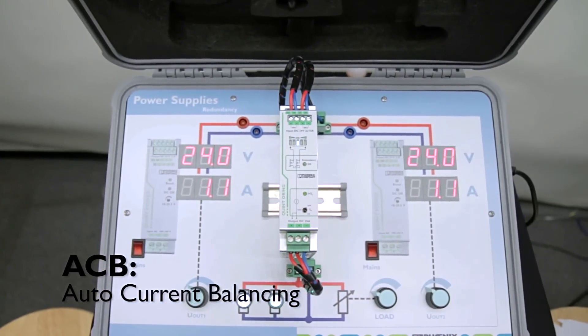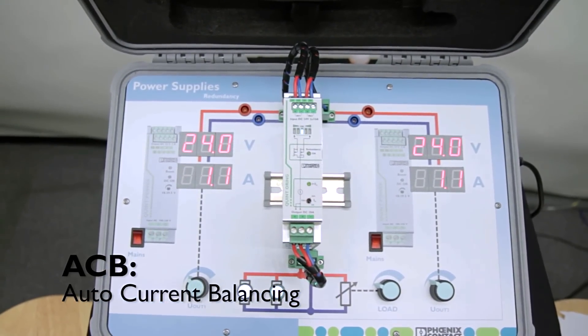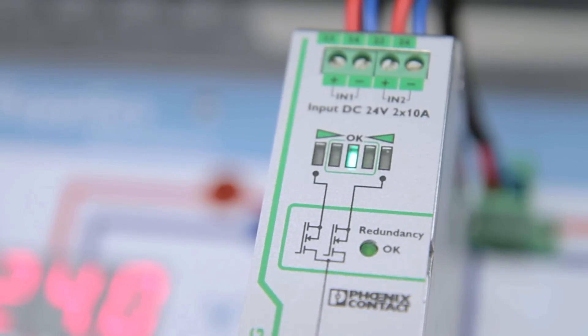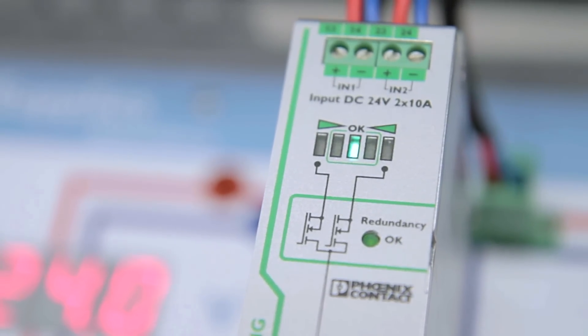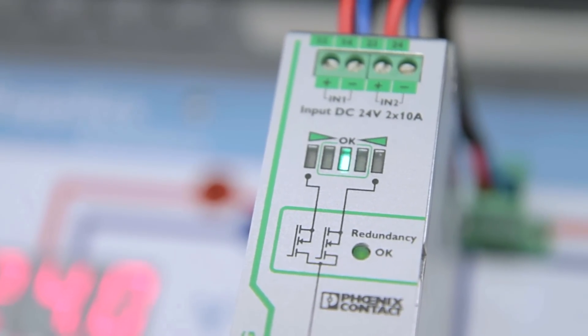The QUINT ORING modules use Auto Current Balancing, or ACB, technology to ensure the power supplies are load sharing evenly. When power supplies are load sharing evenly, they run cooler and double the lifetime of the power system.